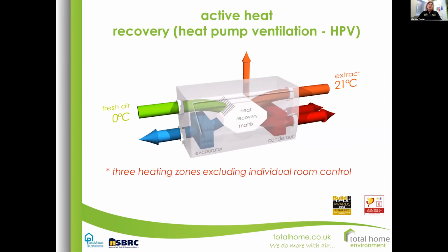So with regards to the HPV and going back to temperatures again, same scenario of 21 degrees in the house and 0 outside. Here you've got your bedroom supply, which comes off before the heat pump gets involved. This is the heat pump here on the left and the right. And then you've got the potential of supplying much higher temperatures to the supply rooms of the house. Now, typically that will probably be about 30, but you can see that that would be a maximum there. And you've got more controllability on temperatures.